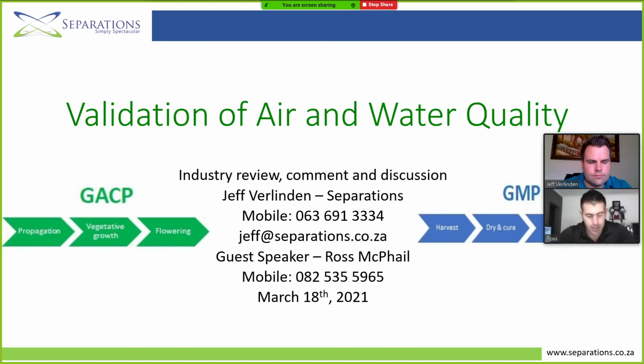I mean, with there, you're going to need to check your dynamic pressure, differential pressure, HEPA filtration, extremely important. Non-viable particle counts, airflow velocity. So this is where the installation qualification, operational qualification, and performance qualification comes in. Number of air changes. How many air changes have been 45, 105? I mean, what scope? At the end of the day, you've also got your ISO 8 grade D.